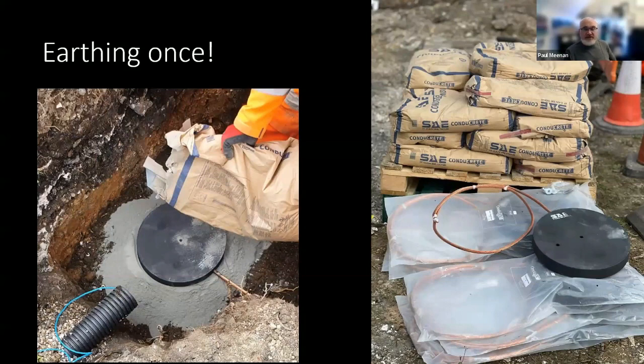One of my favorite things that I've recently been doing over the last few years is getting rid of rods, because they can be inherently dangerous, banging a rod into the ground and hitting a buried service, especially in England where the roads and the streets are quite congested. So I've been trialing some discs, which are carbon coated discs with a copper connection from a company called Earthing Services. They're used in America at the bottom of telecoms poles to give a local earth reference, so similar to a rod but a lot safer. It just bolts onto the bottom of the pole.